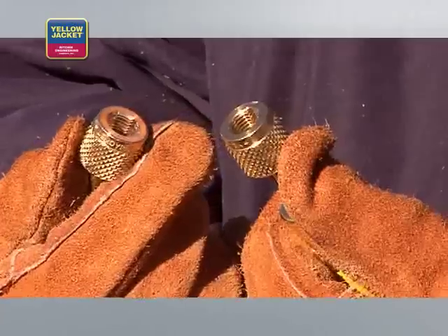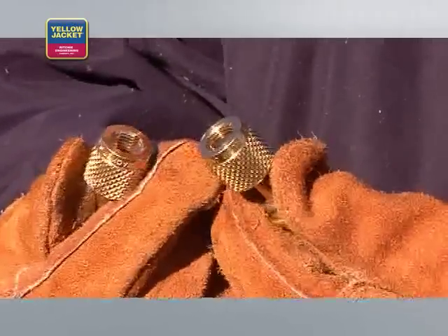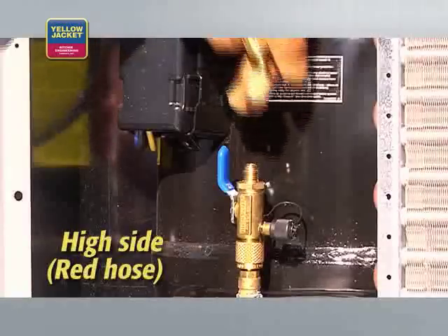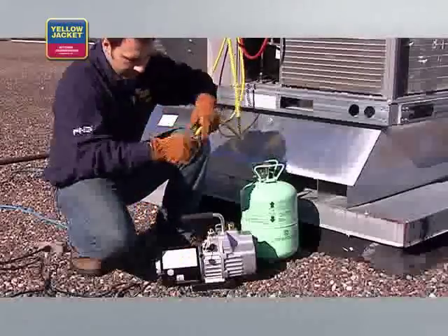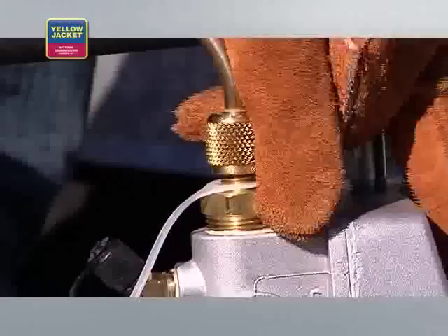Connect the hoses from the manifold to the system. For this demonstration, we're using 3/8-inch hoses for a faster and deeper vacuum. Connect the low side or blue hose to the low side core removal tool, and the high side or red hose to the high side core removal tool. Connect the 3/8-inch hose from the vacuum port on your manifold to the 3/8-inch port on the vacuum pump.